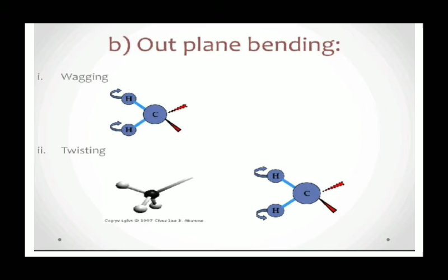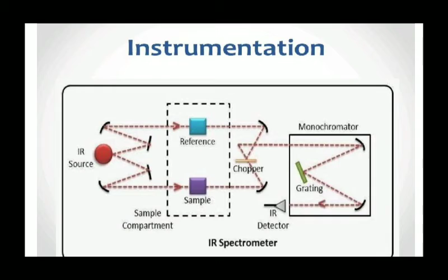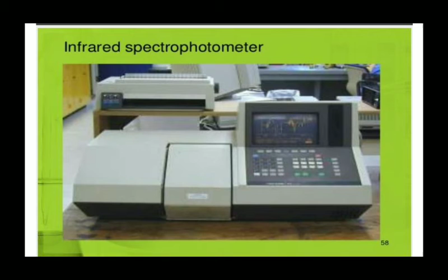Now the instrumentation of the IR spectrometer. You can see there is an IR source, which gives you the IR radiation. Then there is a wavelength selector, or monochromator, by which you can select the wavelength. Then there is a sample holder or cell, also called the sample compartment. There is a detector also, and a recorder is needed. We'll go first with the sources. Here you can see the general instrument of the infrared spectrophotometer.